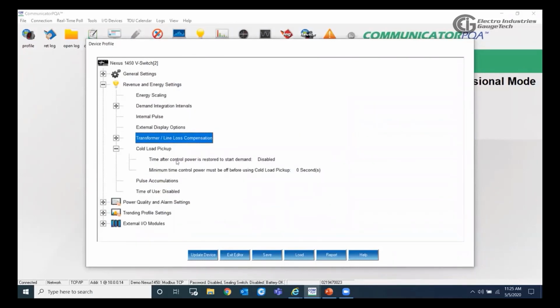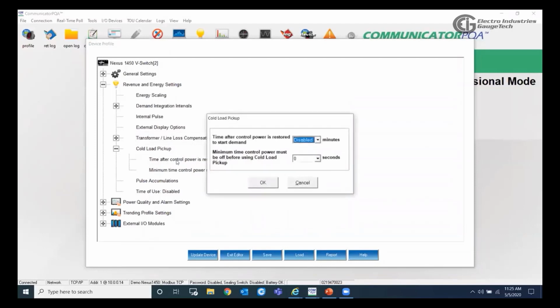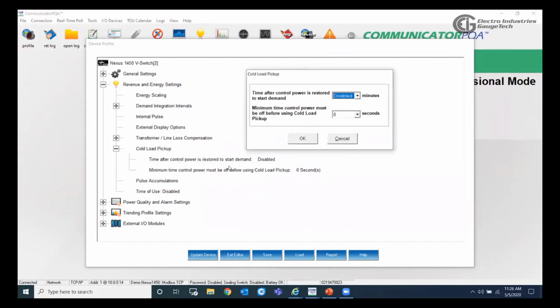The cold load pickup is a function you use with demand, for big industrials and big customer loads. When the power is shut down, you want to give a time before starting to calculate the demand, because after the shutdown there would be a high peak at startup. So you can give that time after the shutdown to not calculate the demand during that time. You can set that for 1 or 2 minutes. So after the shutdown, for 2 minutes, the demand would not be calculated.